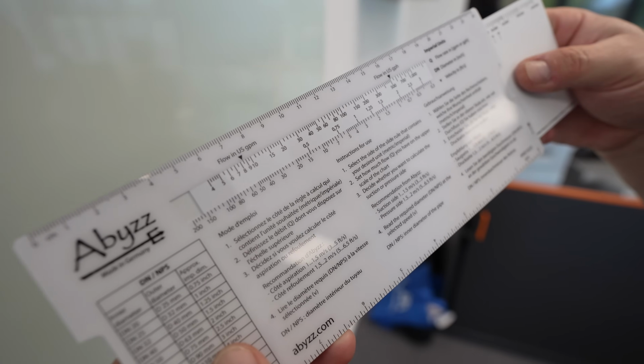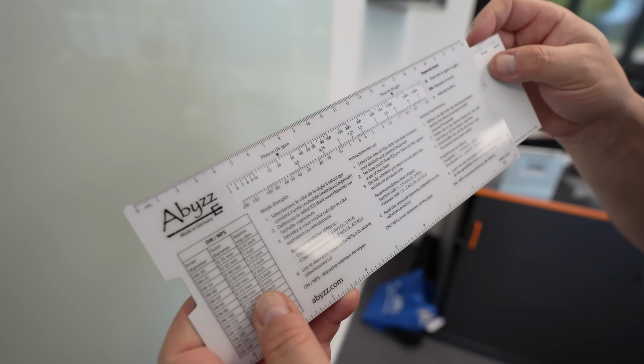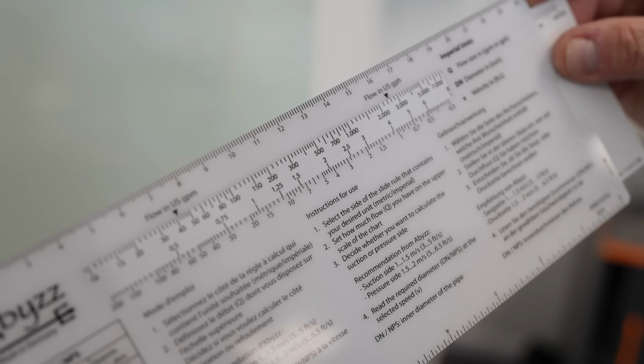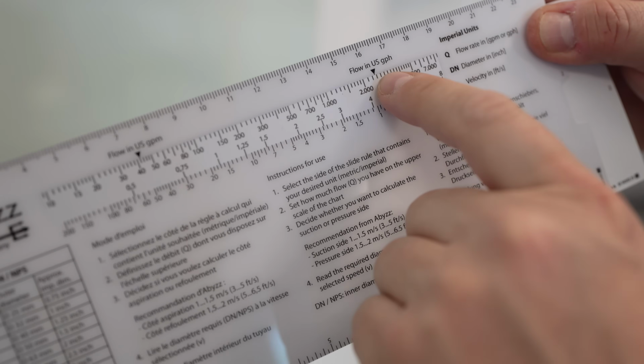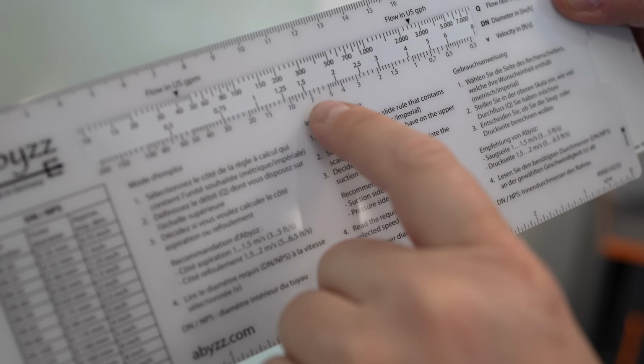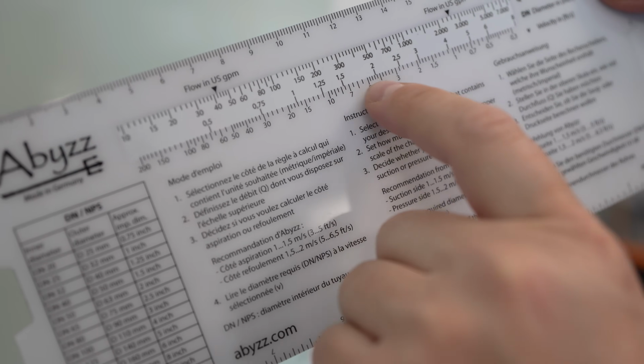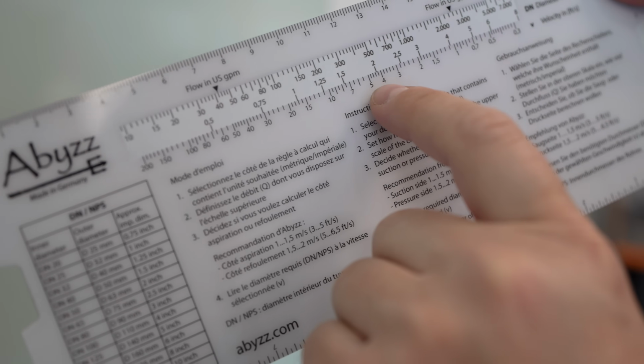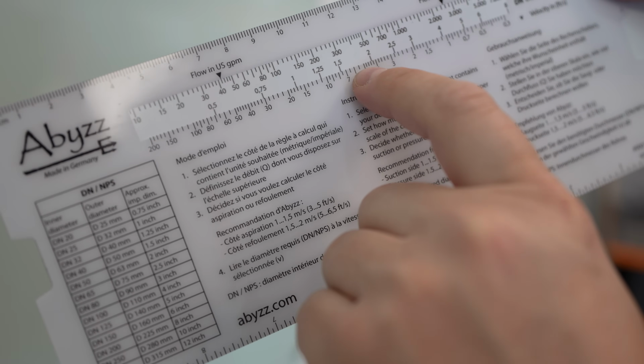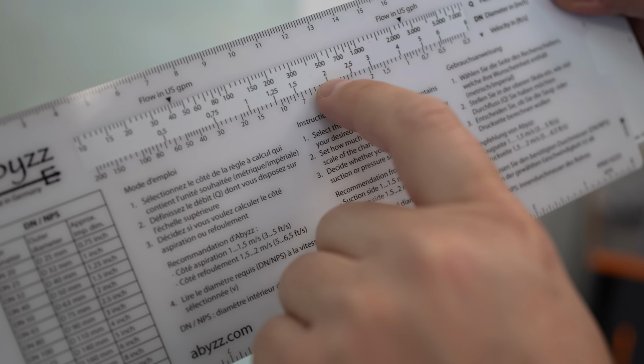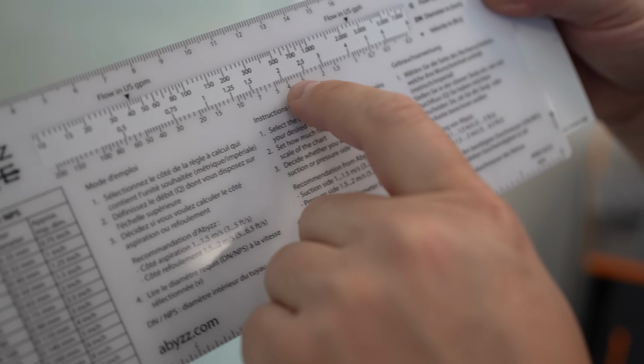Same thing is valid for the gallons per hour, gallons per minute. So if you have 2,500 gallons per hour, that would basically equal our value that we had right now. The velocity is not to exceed 6.5, so we are at 2 inch inner diameter, which will not be enough because of the wall thickness, so you need to step up to 2.5 inch, and that's why you end up at 2.5 inch. Those are things to consider prior to installing the pump and purchasing all the equipment.